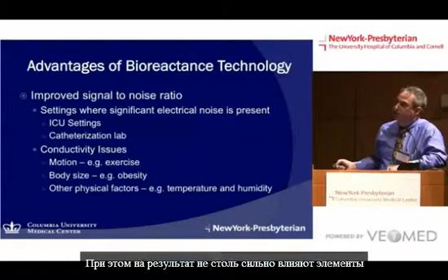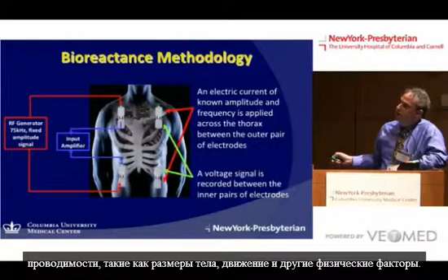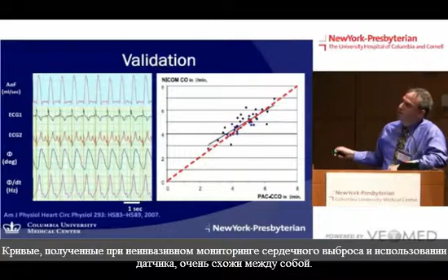The way this device works, pretty simply, is there are four proprietary stickers that go on the patient's chest, typically on the back. As you'll see in a minute, an electrical signal is put in through each side. The voltage is recorded between the two inner pairs, and an input amplifier records this phase shift. These are data from humans on cardiopulmonary bypass. This is a flow probe on the aorta, and you can see the nice flow profile. If you go down to the signal that we're recording, it looks very similar. So you're getting the area under this curve, and the area under the flow probe is indicative of stroke volume. And this correlates very nicely, the NICOM, with PA-derived cardiac output.